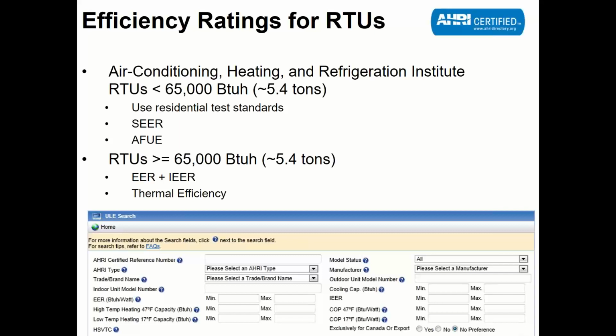It has my fan. It has my indoor evaporator coil. It has my outdoor condenser coil. It has my outdoor fan. And it has my gas heating section, or electric heating section if you choose to do it that way. All in one box. So that's a packaged rooftop unit. A packaged split system would put those things into two pieces. It'd be more like your house. You'd have a condenser coil, a compressor and a condenser fan outside, and inside you'd have an indoor fan, evaporator coil, and a gas heater.